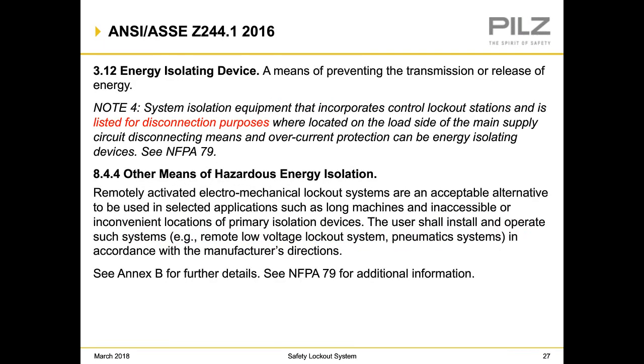So you'll see here also in ANSI Z244.1 and 3.1.2, you can see that system isolation equipment that incorporates control lockout stations and is, again, listed for disconnection purposes. And again, also points out where it's located on the load side of the main and the overcurrent protection. And then down below that, 8.4.4, remote activated electromechanical lockout systems are an acceptable alternative to be used in selected applications such as long machines and inaccessible, inconvenient locations or primary isolation devices. The user shall install and operate such systems in accordance with the manufacturer's directions. And also, then they mentioned Annex B for NFPA 79 for additional information.